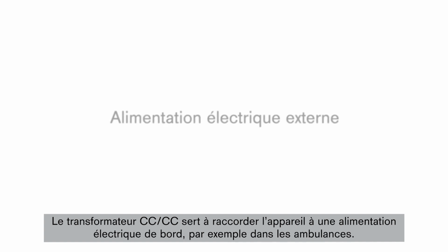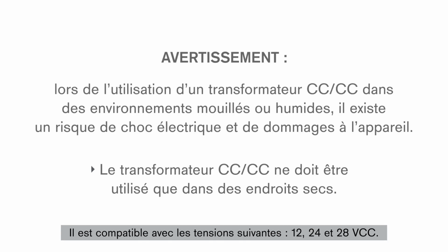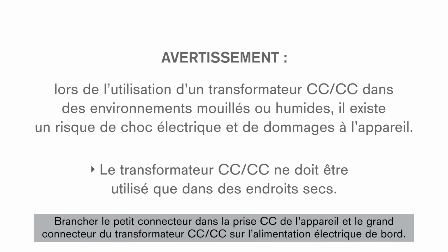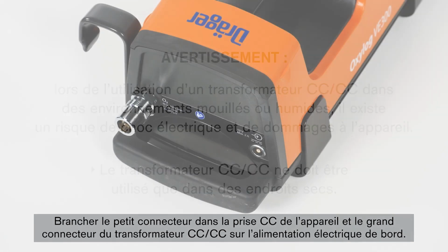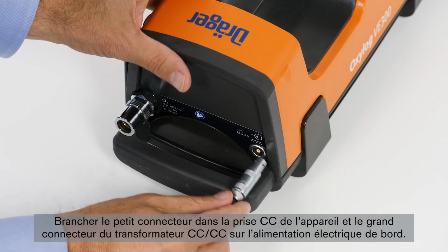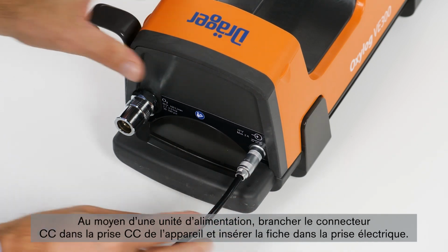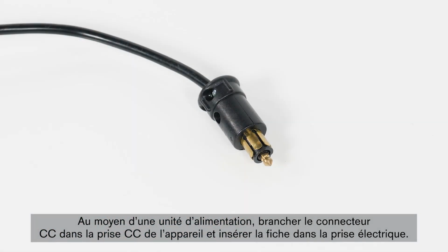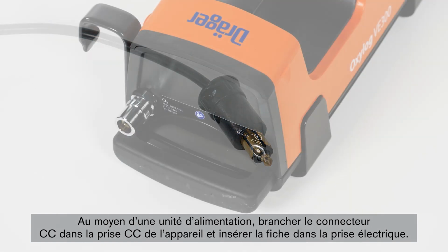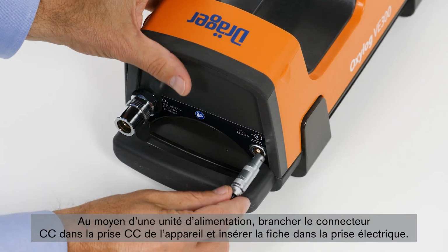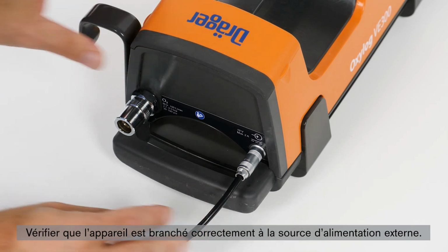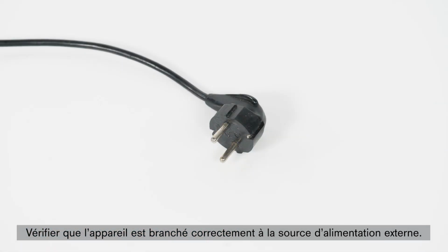The DC-DC converter can be used to connect the device to onboard power supply, such as in ambulances. It can be used with 12, 24 or 28 volts. Plug the small connector into the device's DC socket and the large connector of the DC-DC converter into the onboard power supply. Using a power supply unit, connect the DC connector to the device's DC socket and insert the power plug into the power socket.